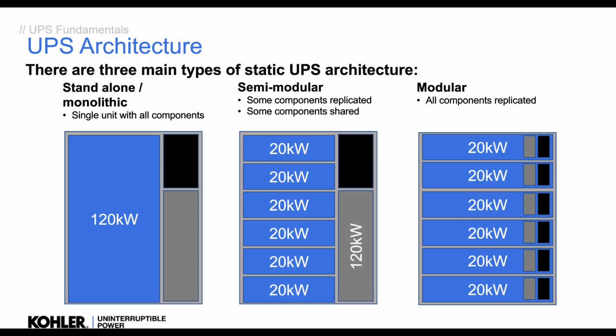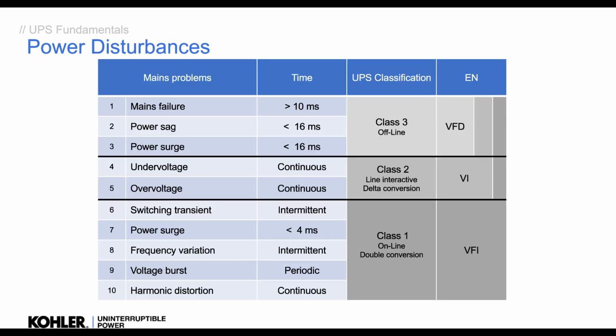And then you're going to get something in between. It could be a semi-modular UPS that has maybe rectifier inverter modules, but the common parts which are shared are the bypass, the control, the display, and things like that. So some are duplicated, some is shared. So it's just understanding the differences. The main difference with the semi-modular to the modular is typically a bypass. So a semi-modular will have one bypass only, whereas a true modular will have distributed bypass to give redundancy on the bypasses as well. So what are we going to protect against? It's regulated by EN 62040.